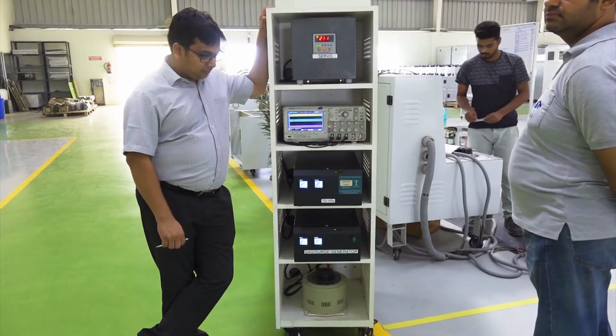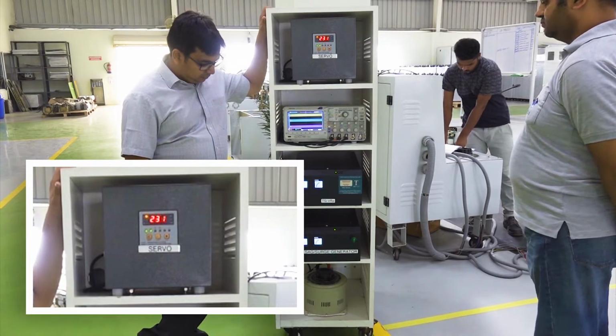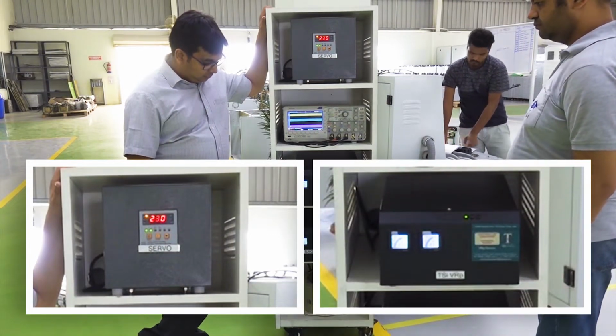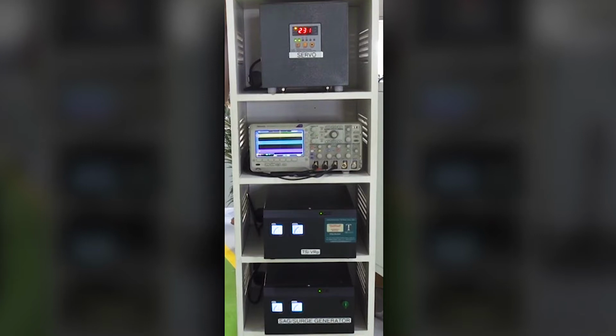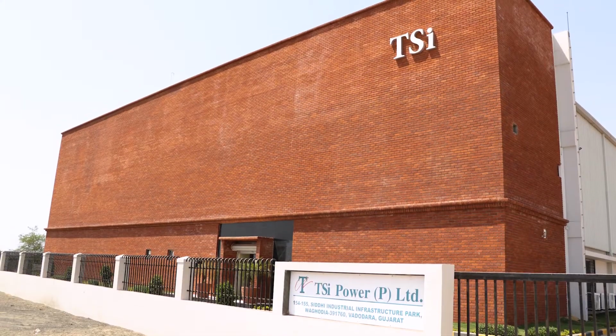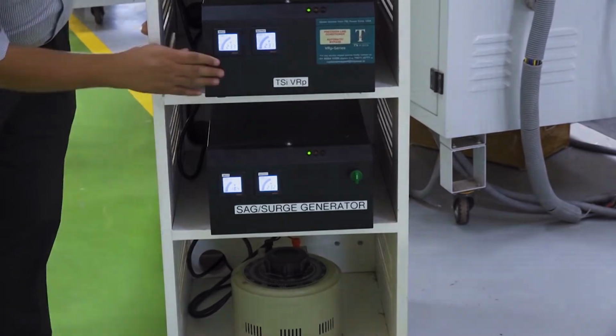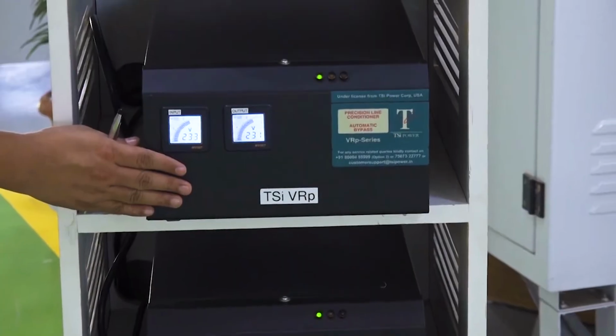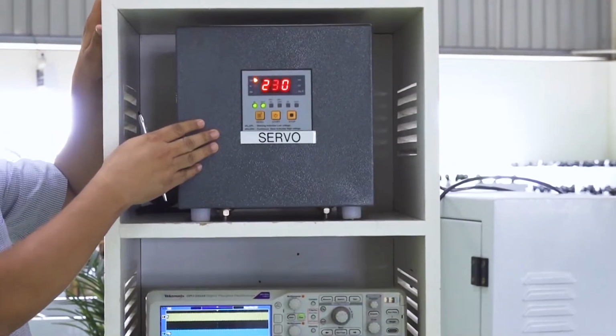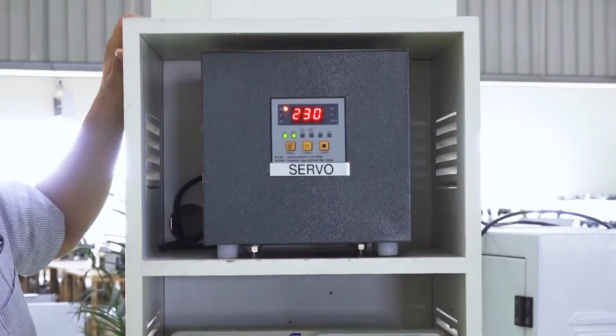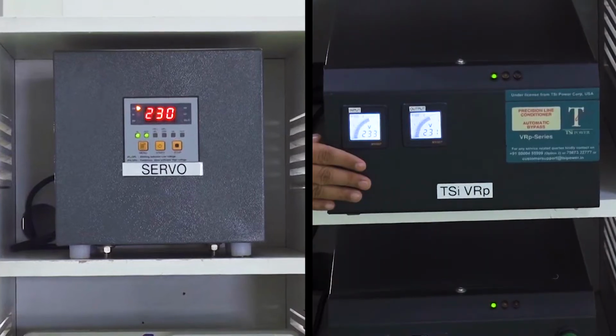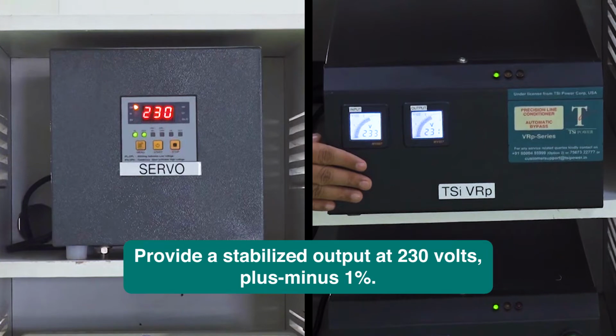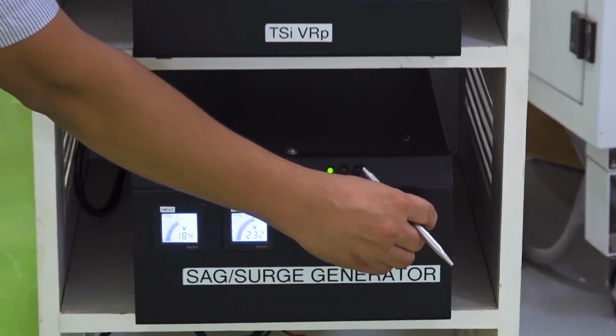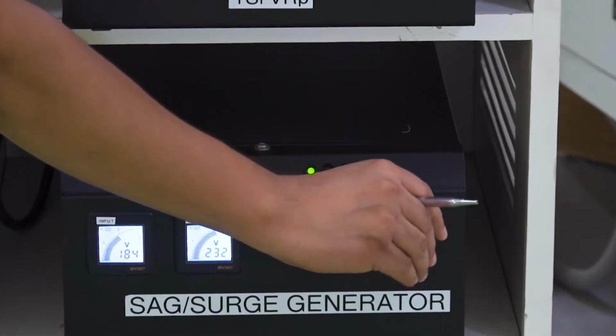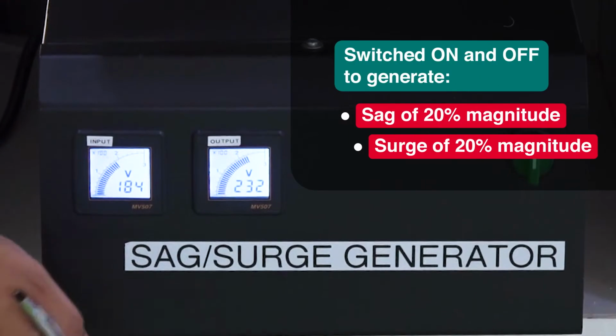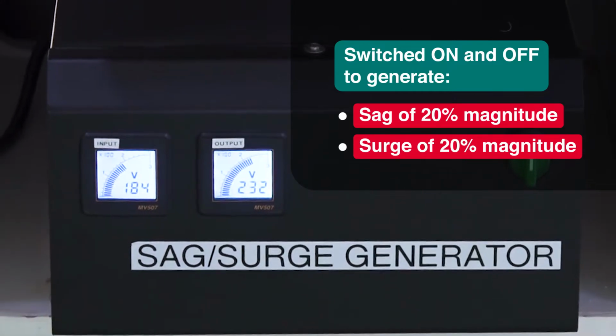Let us now witness a comparison of a typical servo voltage stabilizer with our TSI VRP static voltage regulator at a simple demonstration setup created in our factory at Vadodara in India. Here is a sag surge generator which supplies a nominal 230 volts to a static voltage regulator and also the same 230 volts to a servo voltage stabilizer. Both are designed to provide a stabilized output at 230 volts plus minus 1%. The sag surge generator can be switched on and off by this switch to generate either a sag of 20% magnitude or a surge of 20% magnitude.